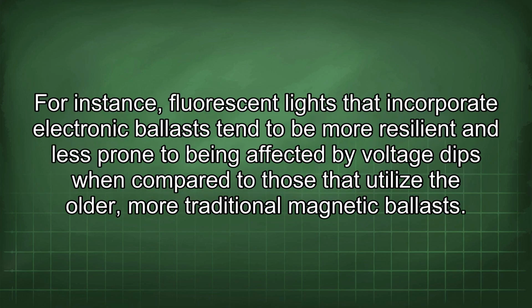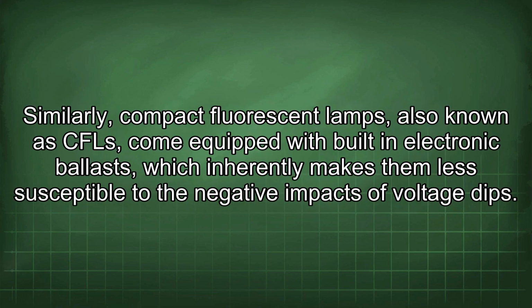For instance, fluorescent lights that incorporate electronic ballasts tend to be more resilient and less prone to being affected by voltage dips when compared to those that utilize the older, more traditional magnetic ballasts. Similarly, compact fluorescent lamps, also known as CFL, come equipped with built-in electronic ballasts, which inherently makes them less susceptible to the negative impacts of voltage dips.